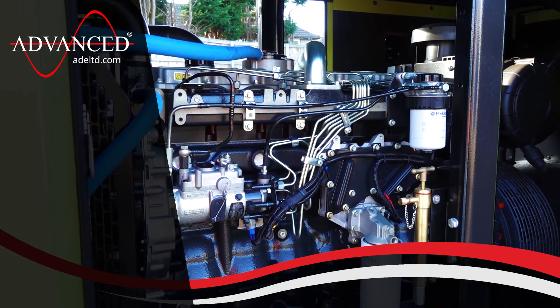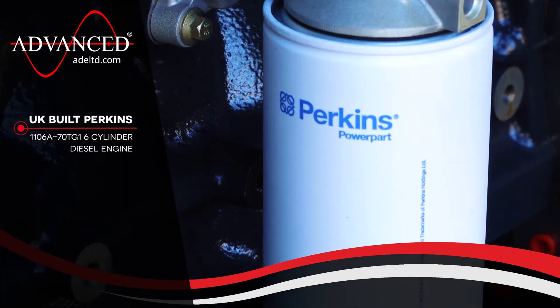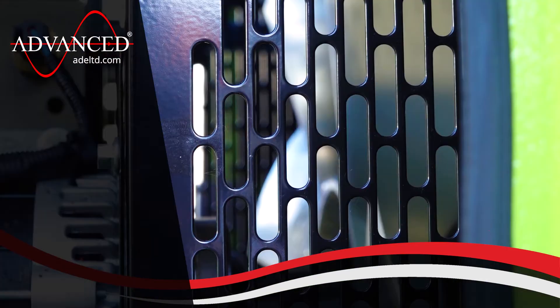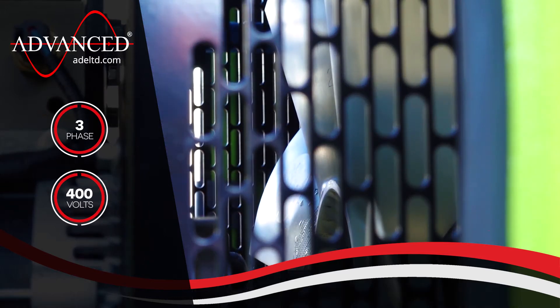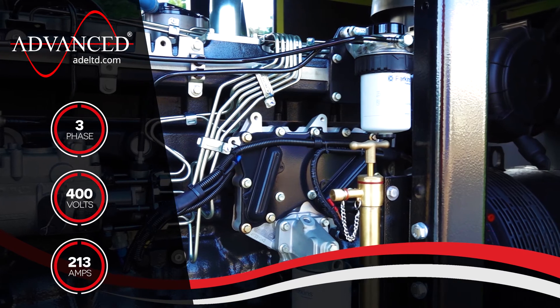This robust genset features a UK-built Perkins 6-cylinder diesel engine, a Mecc Alte alternator and a COMAP automatic control panel. With a three-phase 400 volt output, this unit produces a maximum of 213 amps per phase.